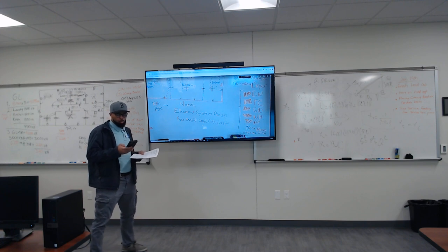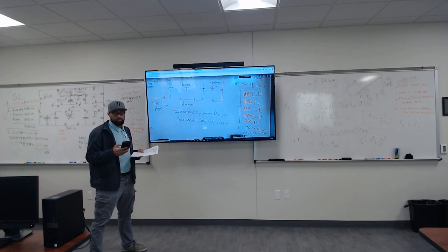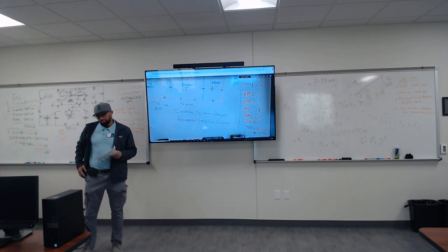I got 10,312, multiply that by 75%. All right, I have 7,734. So the total VA for number four is 7,734. Now, while we're on it, okay, let's see here.